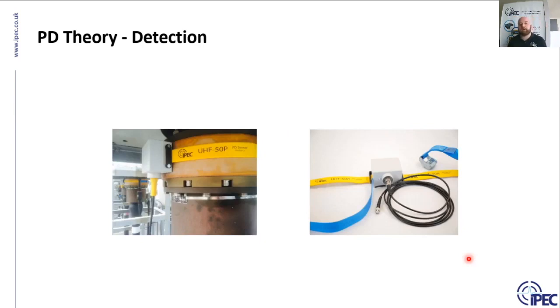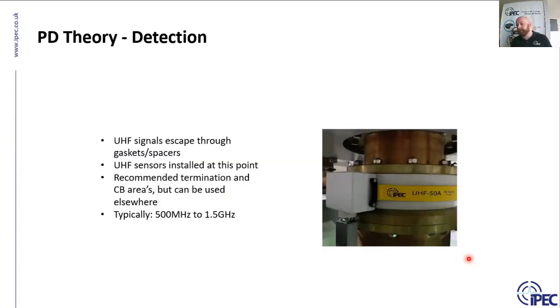Okay, the final sensor type I want to talk about then is UHF sensors, ultra high frequency sensors. The application of UHF tends to focus on EHV GIS, and the problem there is GIS is completely sealed, and so the only signals that escape from GIS are very high frequency, so ultra high frequency, and naturally we use ultra high frequency sensors to detect the PD inside the GIS. Typically our sensors are 500 meg up to 1.5 gigahertz, but they could be even more. Actually, IPEC sensors are about 300 meg up to about 2 gigahertz, and we install them on the barriers.